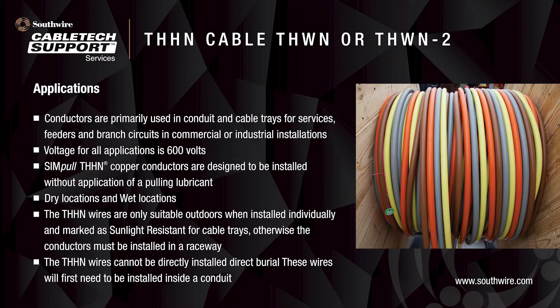Some of the applications for THHN include use in conduit and cable trays for services, feeders, and branch circuits in commercial or industrial installations. Southwire SIMpull THHN copper conductors are designed to be installed without application of a pulling lubricant. THHN can be used in outdoor locations when installed individually and marked as sunlight resistant for cable trays; otherwise, the conductors must be installed in a raceway. THHN wires cannot be directly installed underground — they will first need to be installed inside a conduit. For more information about uses and applications, please review NEC Article 310.